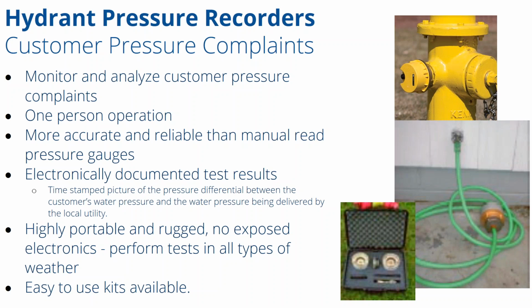So for customer complaints, what you would use the hydrant pressure recorder for is that you would hook it up with a garden hose adapter to the customer's house, and you would open the water faucet as high as it can go. And then you would also connect the hydrant pressure recorder on the closest fire hydrant that is connected to the same water main line. And then you let it gather data for however long of a time that you feel you would need to get the information. This could be 10 minutes or this could be several days. We have customers that do both.